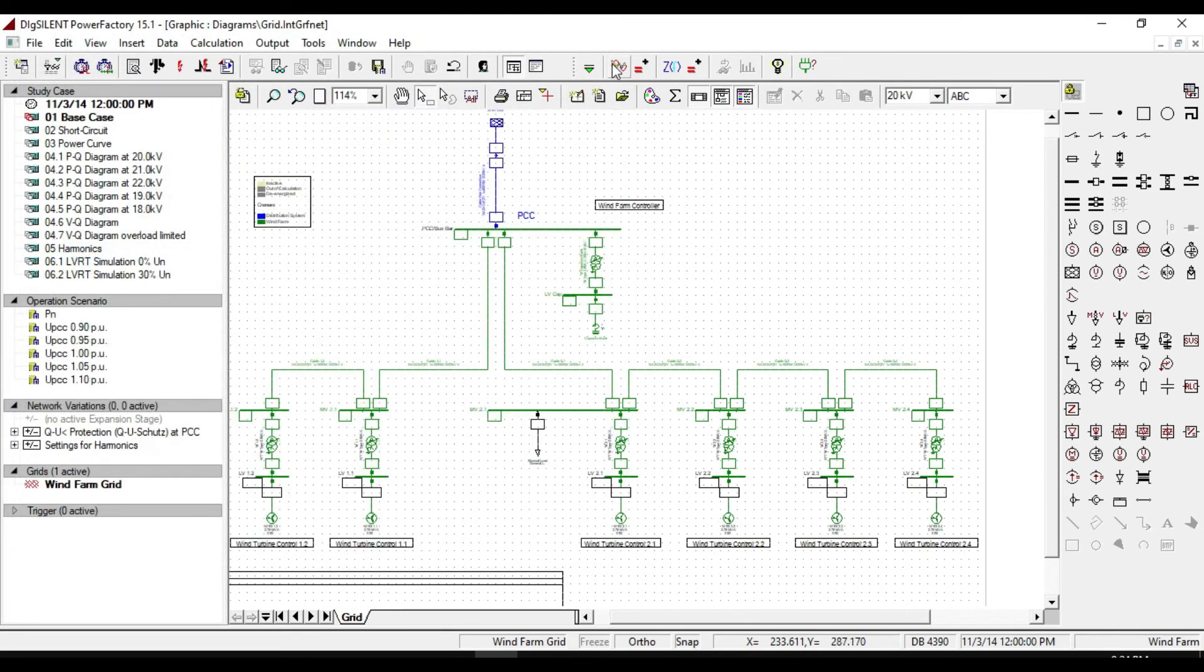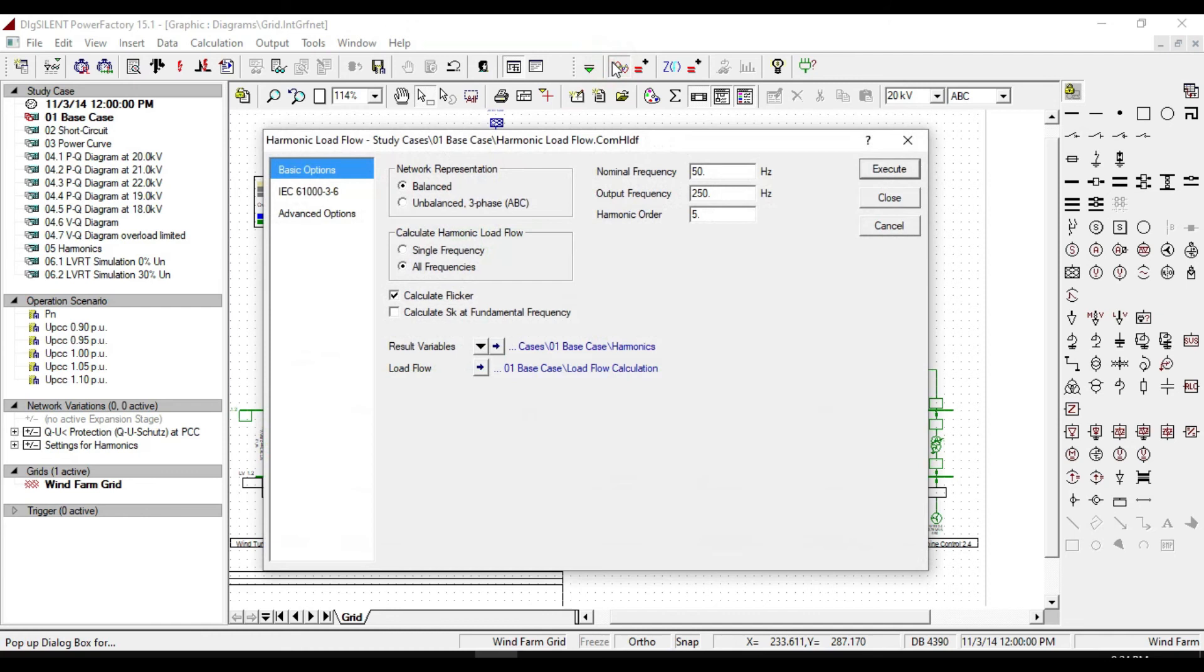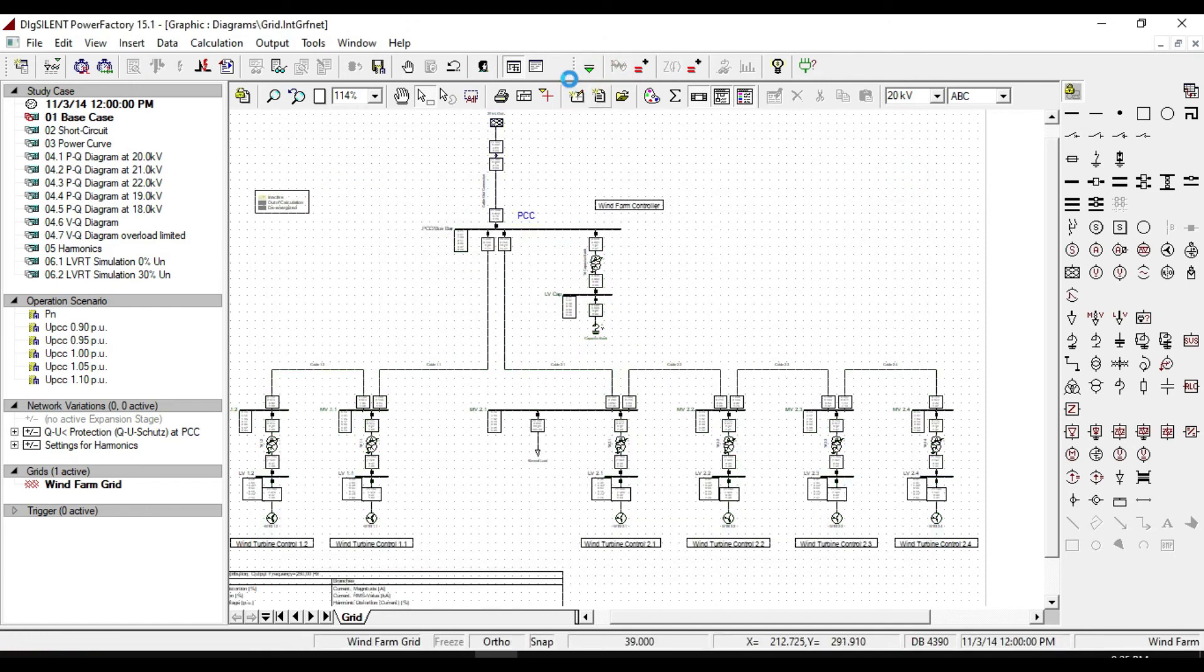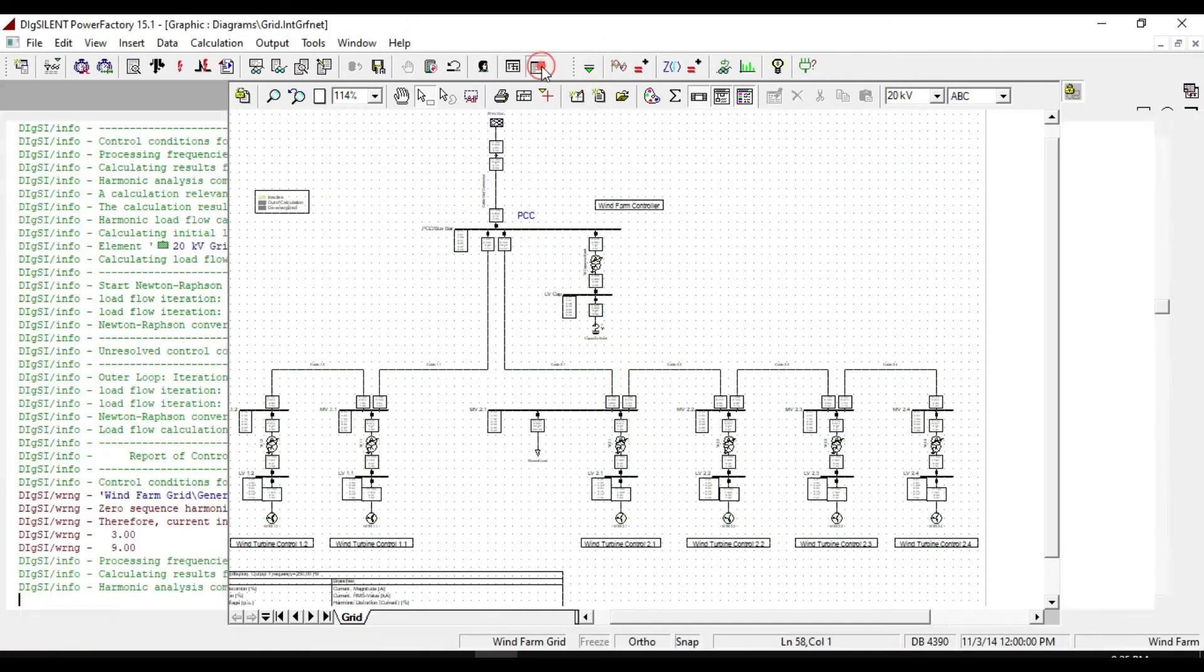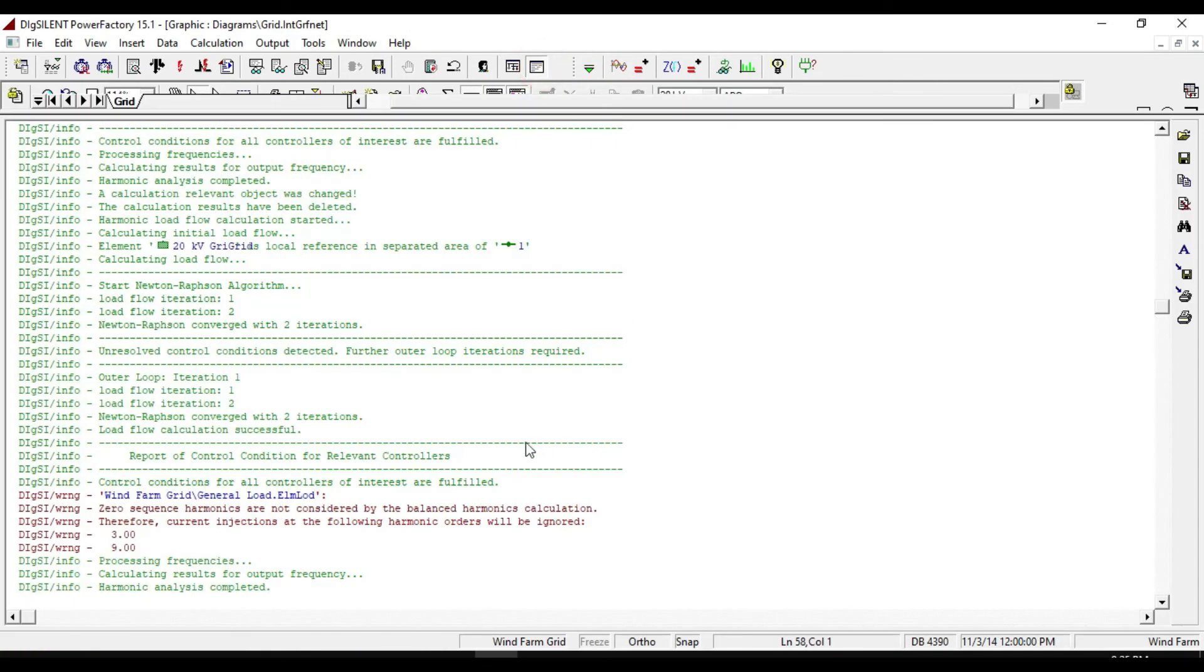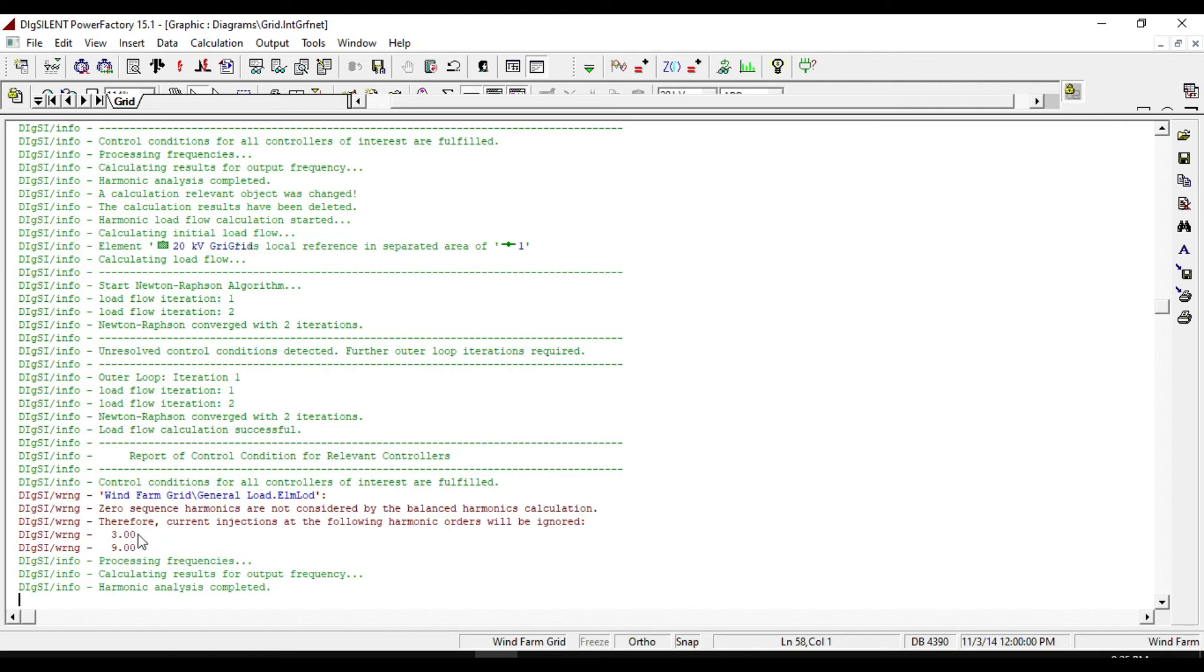And calculate harmonic load flow. As you see, there is an error about the general load. It says that zero sequence harmonics are not considered by balanced harmonic calculation. Therefore, current injections at the following harmonic orders will be ignored.